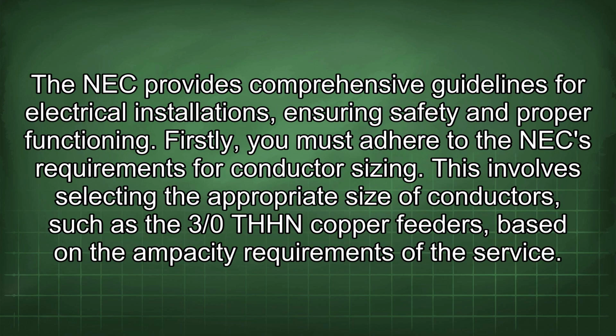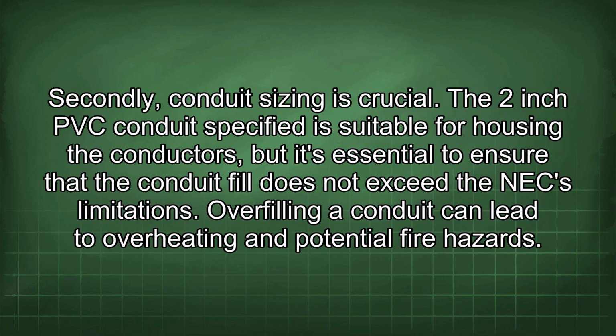The NEC provides comprehensive guidelines for electrical installations, ensuring safety and proper functioning. Firstly, you must adhere to the NEC requirements for conductor sizing. This involves selecting the appropriate size of conductors, such as the 3/0 THHN copper feeders, based on the ampacity requirements of the service. Secondly, conduit sizing is crucial. The 2-inch PVC conduit specified is suitable for housing the conductors, but it's essential to ensure that the conduit fill does not exceed the NEC limitations. Overfilling a conduit can lead to overheating and potential fire hazards.